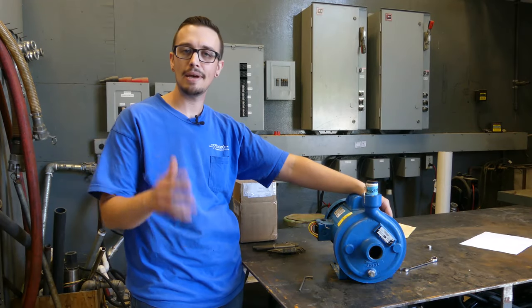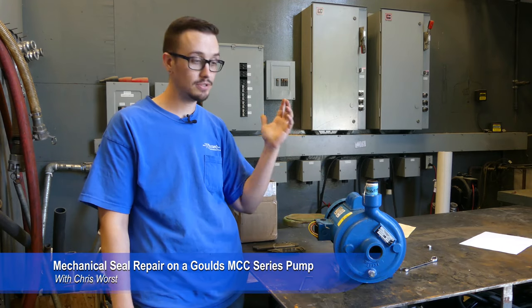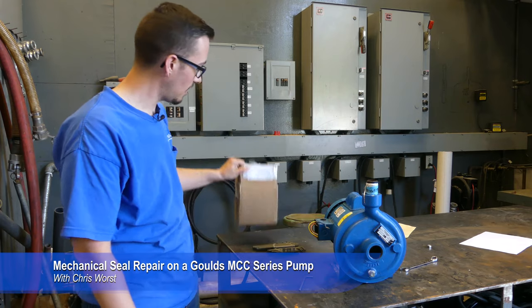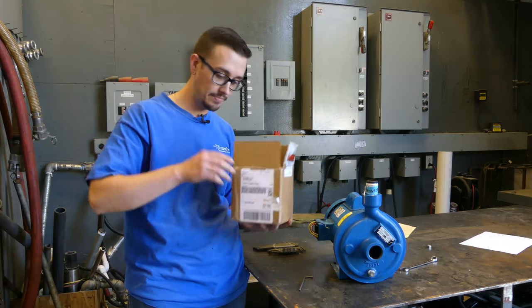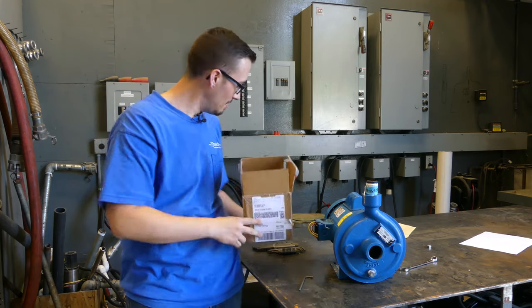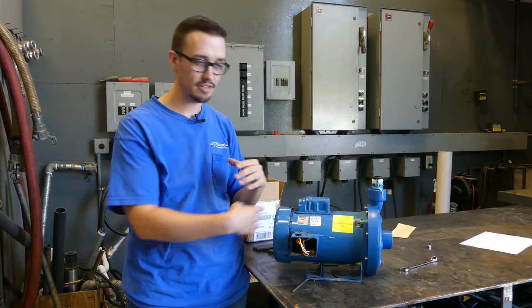Hey guys, Chris with Thirsty Worst here. Welcome back — this is part two of the Goulds pump. Jeremy went ahead and hooked this thing up to water and it was still leaking, and the only thing we could come up with is it's got to be the shaft seal. So we've got the shaft seal here and we are going to put that in. We've got to take these bunch of allen heads off again and take it apart.